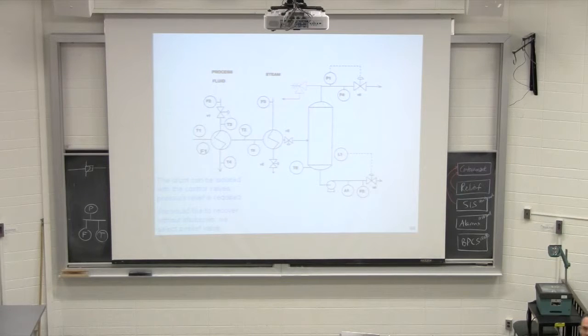Now, typically, you won't put this relief valve right into the vessel. When you've bought the vessel from the supplier, it's a closed, single unit with several pipes leading out. And so you could put this relief valve either on the pipe leaving or on one of the other ports on that vessel. But it's got to be in the direct path. Obviously, no valves between this and the relief valve. And then you send that off to containment in a suitable way.